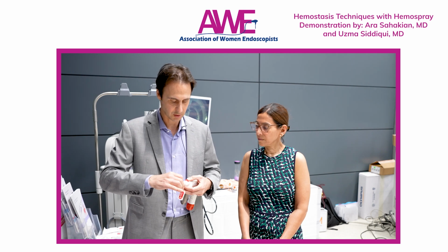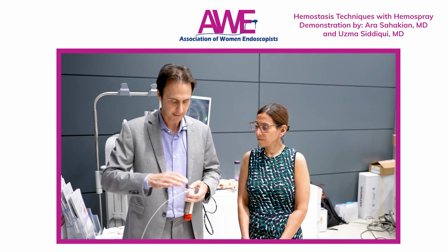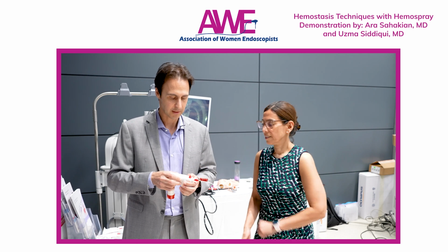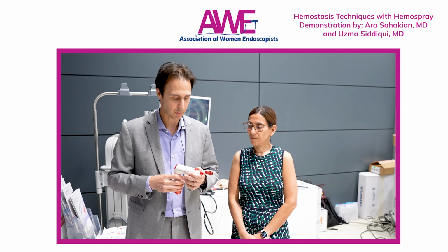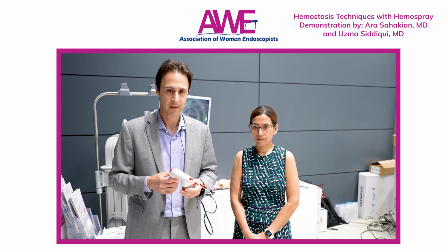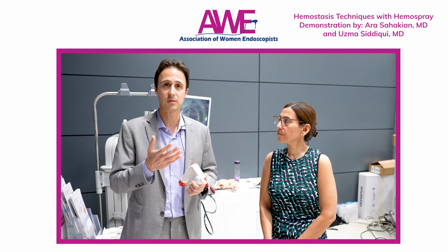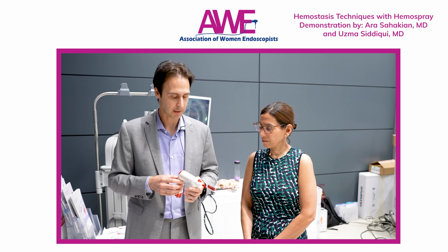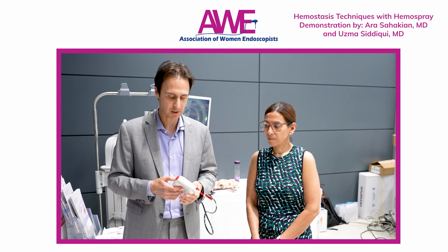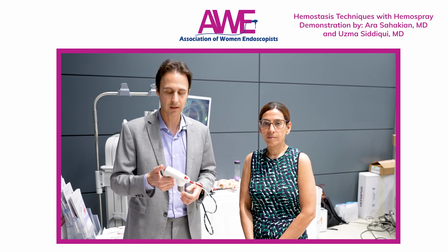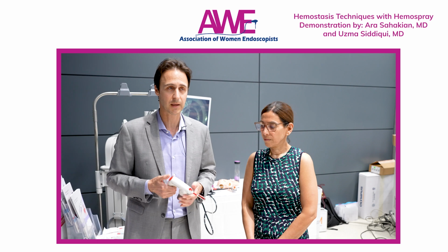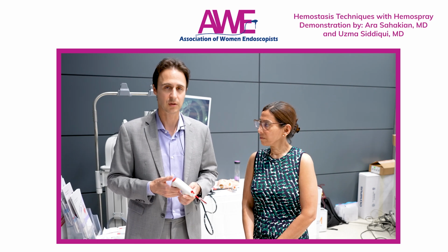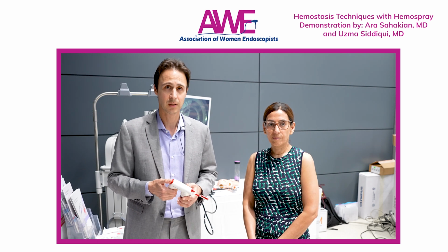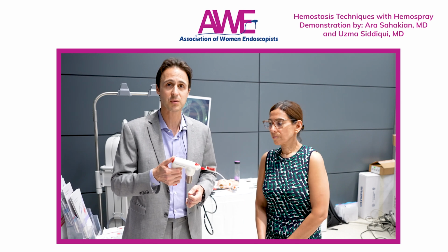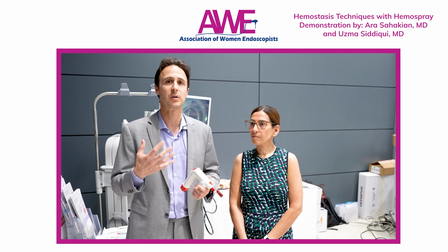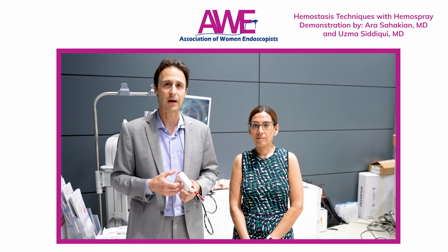And then, of course, when you're ready to spray, we have our valve here, and we're going to point the valve forward to get ready to spray. And the endoscopist obviously is going to aim the catheter in the patient, and your technician or your fellow will go ahead and press the trigger button to go ahead and fire the hemostatic material. Generally, we're using small pulses, and that can kind of help with your visualization to avoid it getting too cloudy.